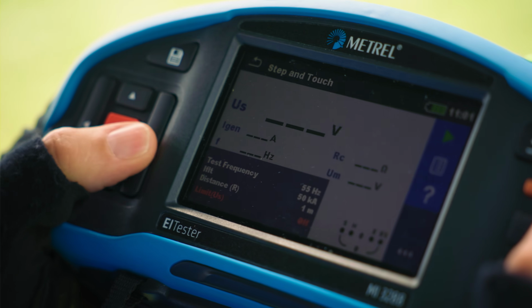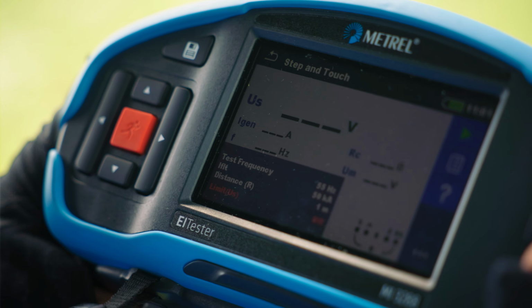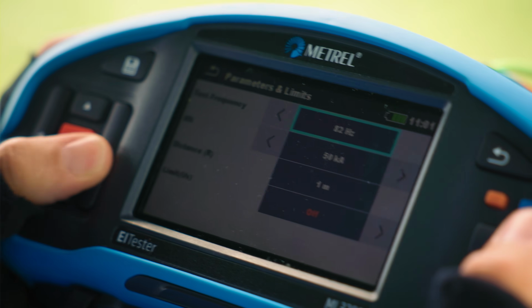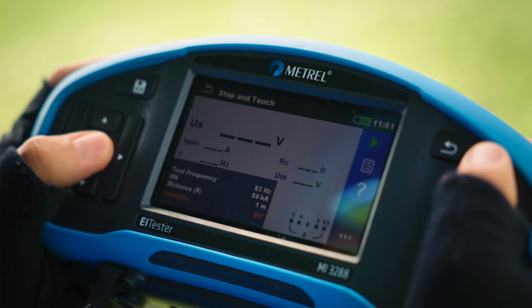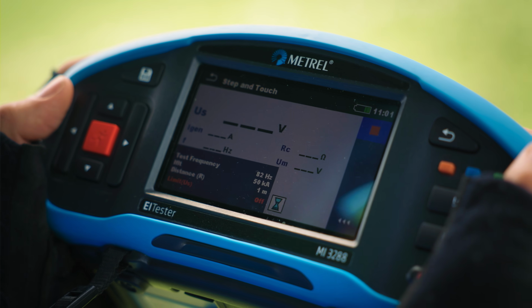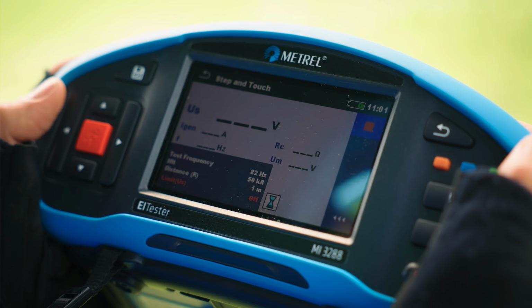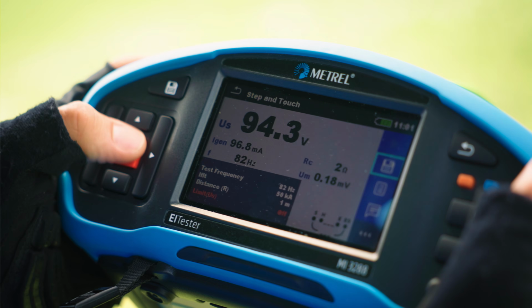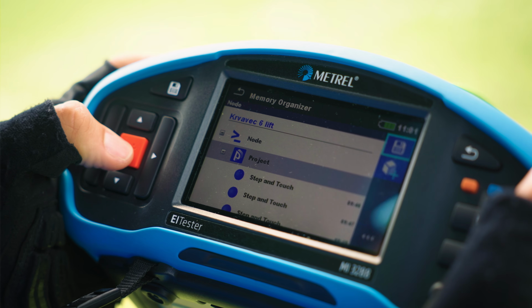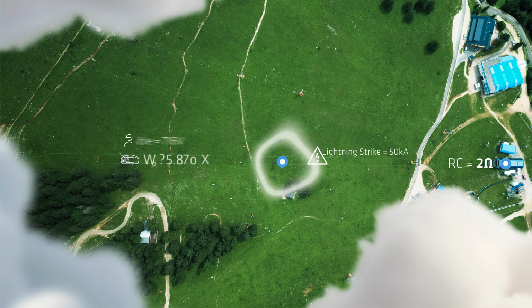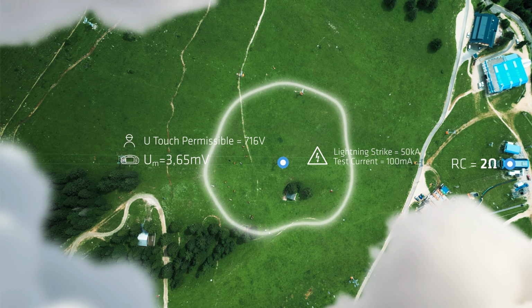These measurements do more than confirm compliance. They reveal risks caused by poor installation, corrosion, or environmental wear. When results stay below 716 volts, we know the system offers a safe response during a lightning strike.